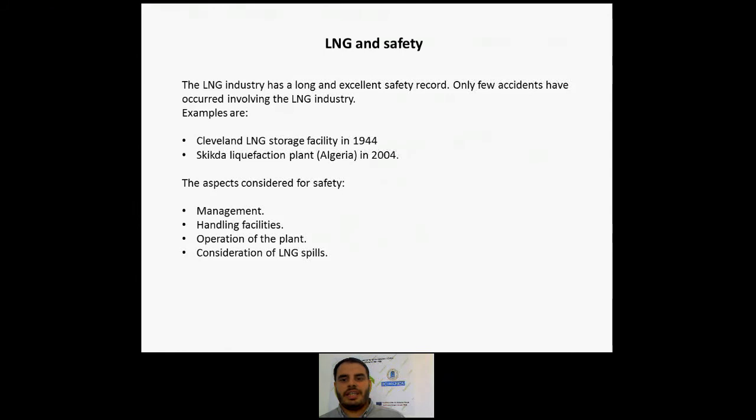First, responders need to be trained to treat such a spill, because pouring water on an LNG pool results in a large increase of LNG vaporization. A better approach is to confine a spill with quick, simple methods, such as placing sandbags in ditches. While application of firefighting foam is not too effective once an LNG pool fire is ignited, it can limit the evaporation rate of a pool prior to ignition.